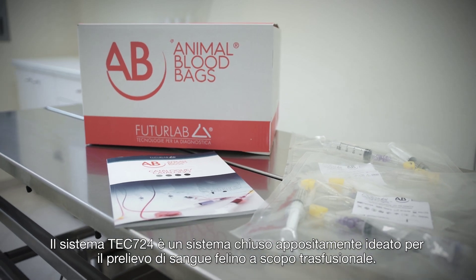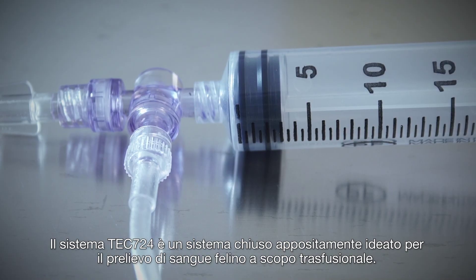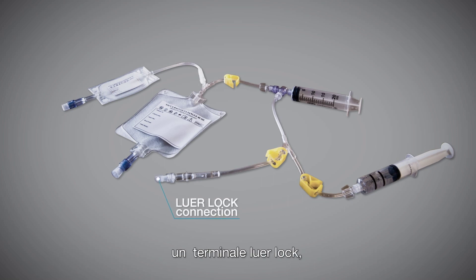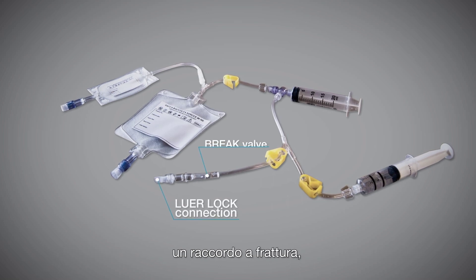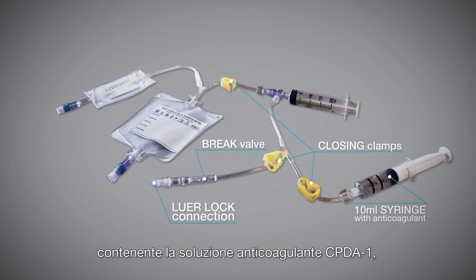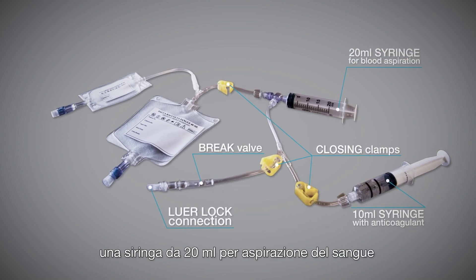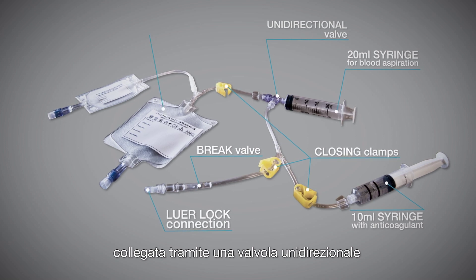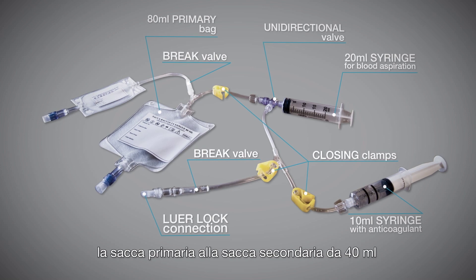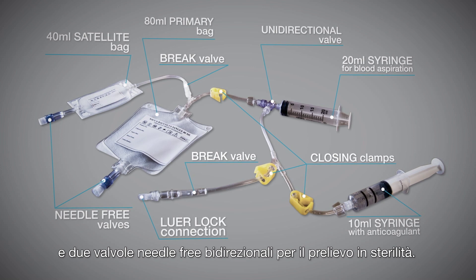TEC724 is a closed system specifically designed for the collection of feline blood for transfusion purposes. The gamma ray sterilized kit is composed of a luer lock connection, one break valve for tubing, three closing clamps, a 10 ml syringe containing the anticoagulant solution CPDA-1, a 20 ml syringe for blood aspiration connected through a unidirectional valve to the 80 ml primary bag, another break valve for tubing that connects the primary bag to a 40 ml satellite bag, and two needle-free valves for aspiration of blood in sterility.